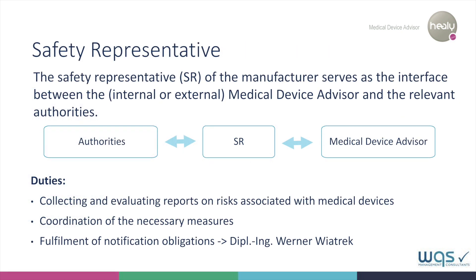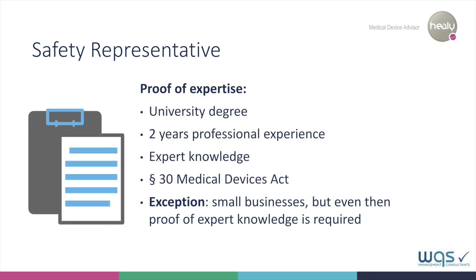Let's now talk about the role of the safety representative, or SR. As a mediator between the authorities and the MDA, the SR has the following tasks: he or she collects and evaluates reports regarding the risks of medical devices, coordinates any necessary measures, and fulfills the notification duties. The SR at Healy World is engineer Werner Vietrich. The prerequisites to become an SR are graduation from university and at least two years of professional experience acquiring the specialist knowledge required by paragraph 30 of the German Medical Devices Act.